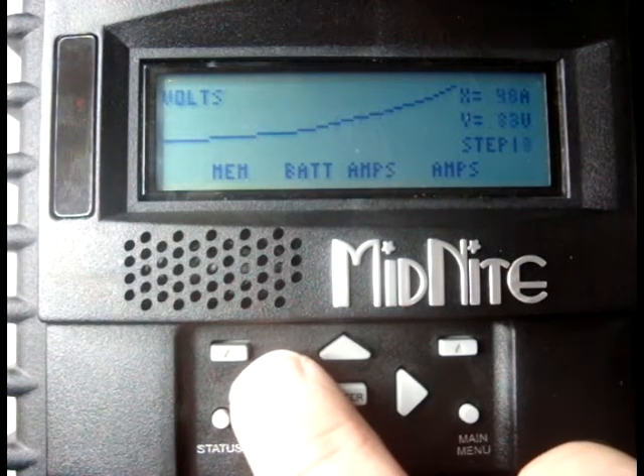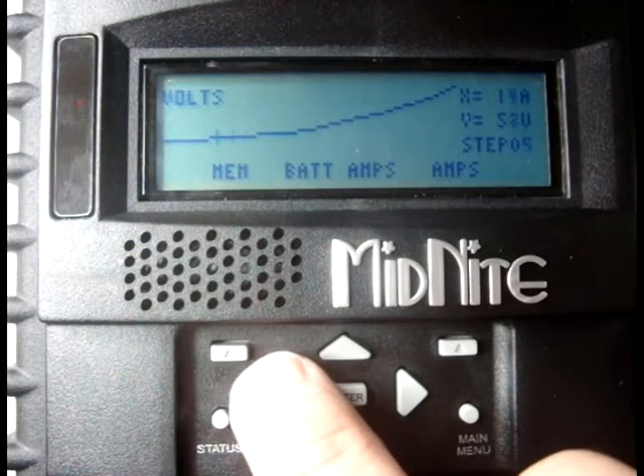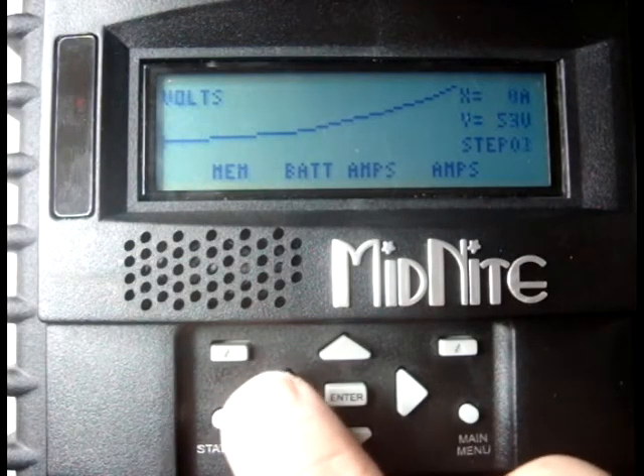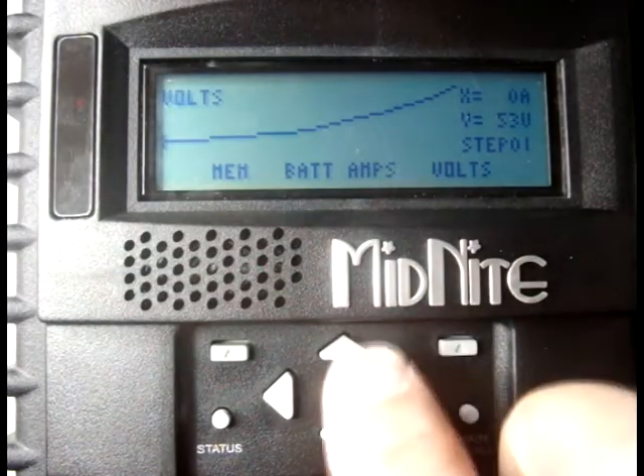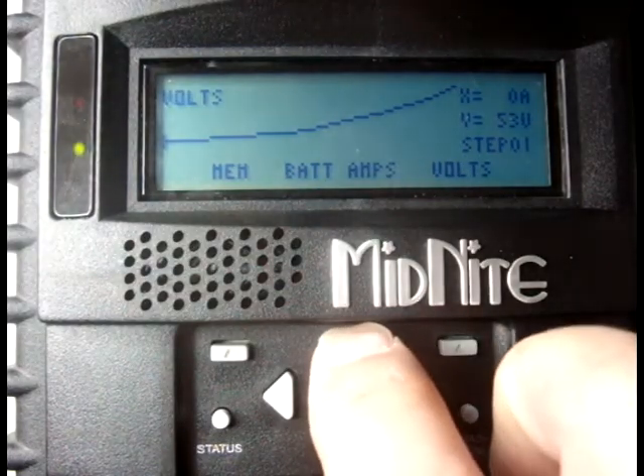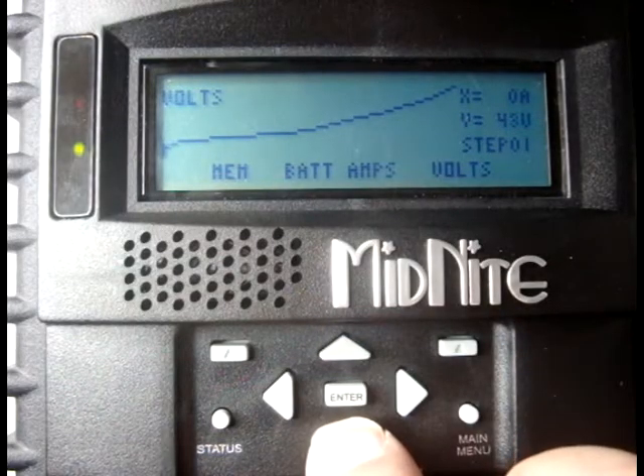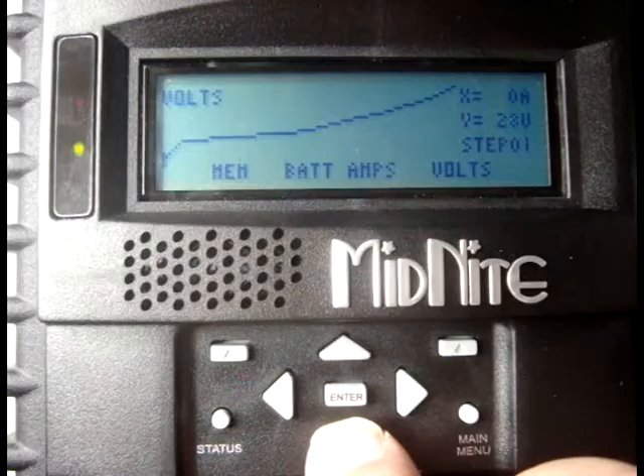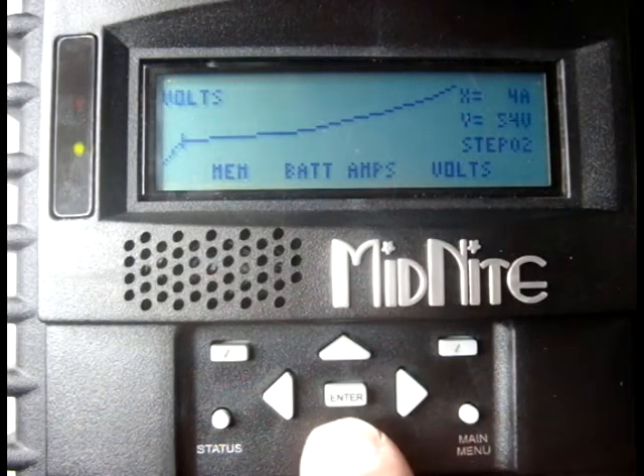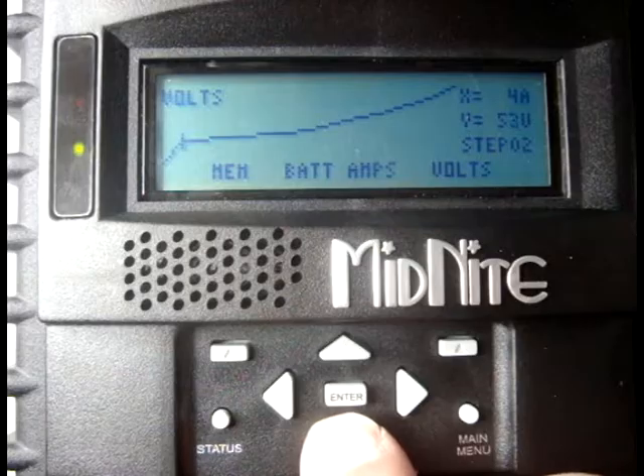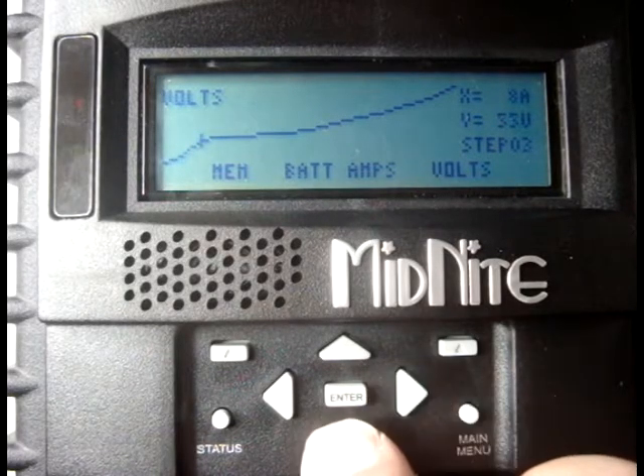You can move left or right from one step to the next using the left and right keys, and you can vary each individual point's voltage or current in amps using the up and down keys. The Classic will start operating when the turbine input voltage rises above step one's voltage set point at zero amps battery current. This point will become the cut-in voltage and should be set somewhat above the maximum expected battery voltage.